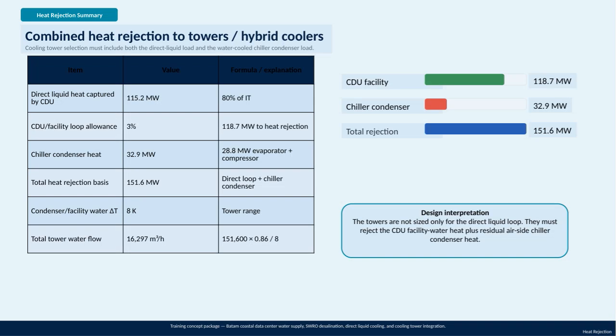Here, we're looking at the heat rejection summary for the cooling system. The key point is that when selecting cooling towers, we need to account for both the direct liquid heat load from the IT equipment and the heat from the water-cooled chiller condenser. The direct liquid cooling system captures about 115.2 megawatts, which is 80% of the IT load. We then add a small allowance of 3% for facility loop, bringing that number to 118.7 megawatts directed towards heat rejection. The chiller condenser adds another 32.9 megawatts, which combines heat from the evaporator and compressor.